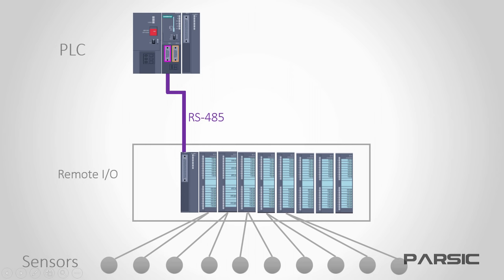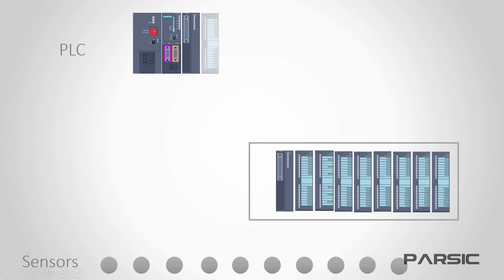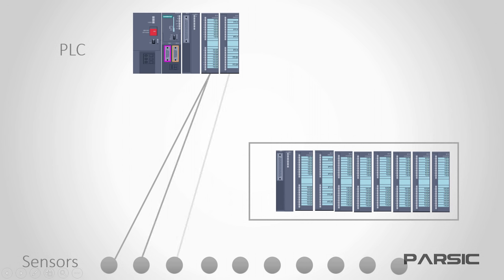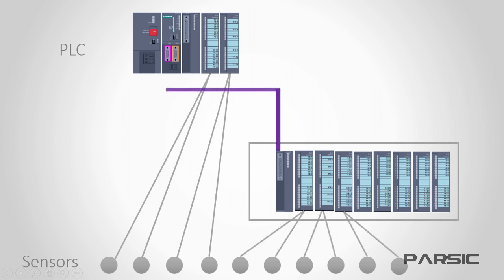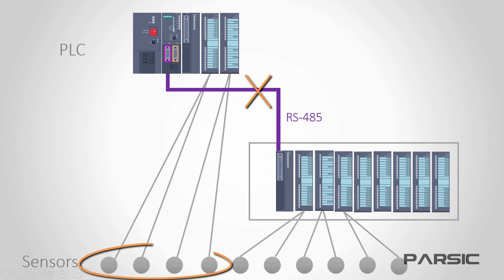To prevent this problem, some applications have some of the main signals connected directly to the PLC, and transfer the rest of the signals using Profibus DP. With this wiring configuration, even if the data cable goes down for any reason, the signals from important facilities are not lost. This method is called hybrid.